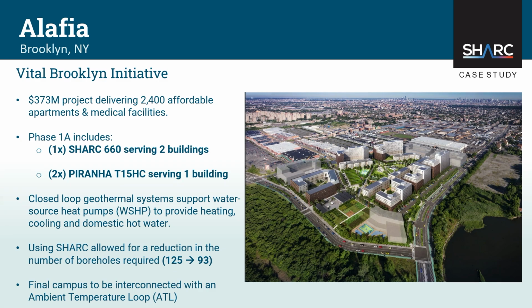Passive house design buildings are very cooling dominant. So by putting the SHARC into the system and using it to pick up just the peak loads, this is wild, just the peak loads of those few really hot days in the summer, they're able to right-size the bore field from about 125 boreholes down to 93. So there's a massive first cost savings for the project. And now moving forward, by pushing and pulling energy in and out of that sanitary stream, we're able to keep that bore field dialed into that perfect temperature around 68 to 82, depending on what you need, to keep the heat pumps operating at their maximum capacity and efficiency. So a really, really fantastic project.